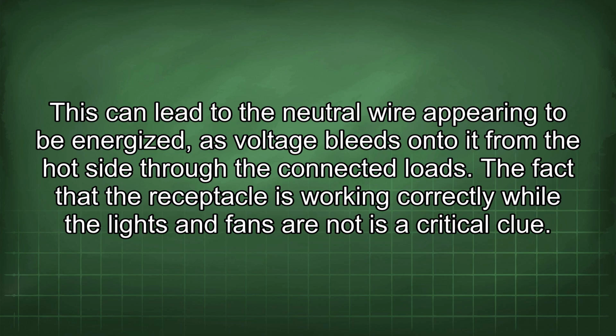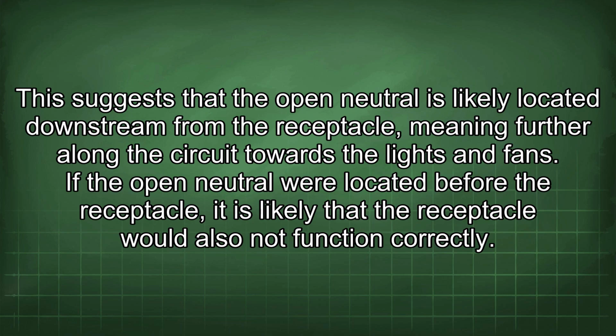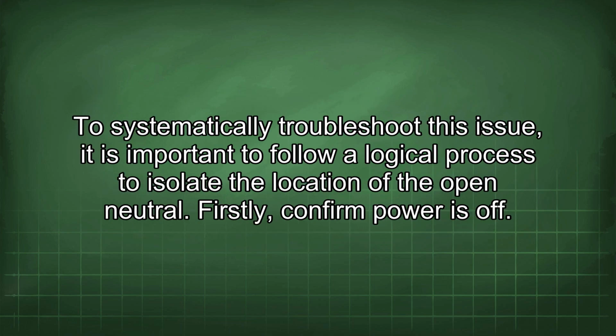through the connected loads. The fact that the receptacle is working correctly while the lights and fans are not is a critical clue. This suggests that the open neutral is likely located downstream from the receptacle, meaning further along the circuit towards the lights and fans. If the open neutral were located before the receptacle, it is likely that the receptacle would also not function correctly. To systematically troubleshoot this issue, it is important to follow a logical process to isolate the location of the open neutral. Firstly, confirm power is off.